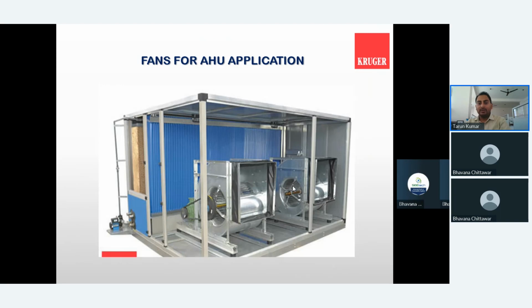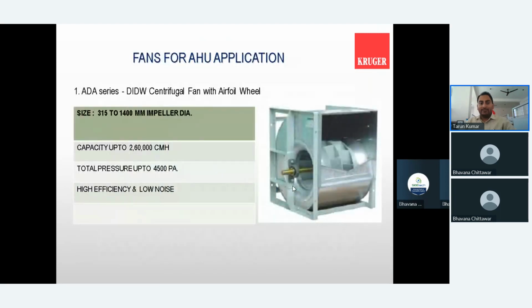AHU, air handling unit, everyone knows. It is for air circulation, for better comfort cooling, and for air handling units we use the centrifugal fan. Here you can see the centrifugal fan also has the ADA fan, as I told you, aerofoil curve, backward curve, and forward curve. Basically aerofoil and backward curve have almost the same configuration. The difference is that aerofoil has some better curvature over the blade, which gives better efficiency than the backward curve fan. And there is a difference between forward curve and backward curve fan: forward curve is made of GI material, whereas backward curve is made of MS material.